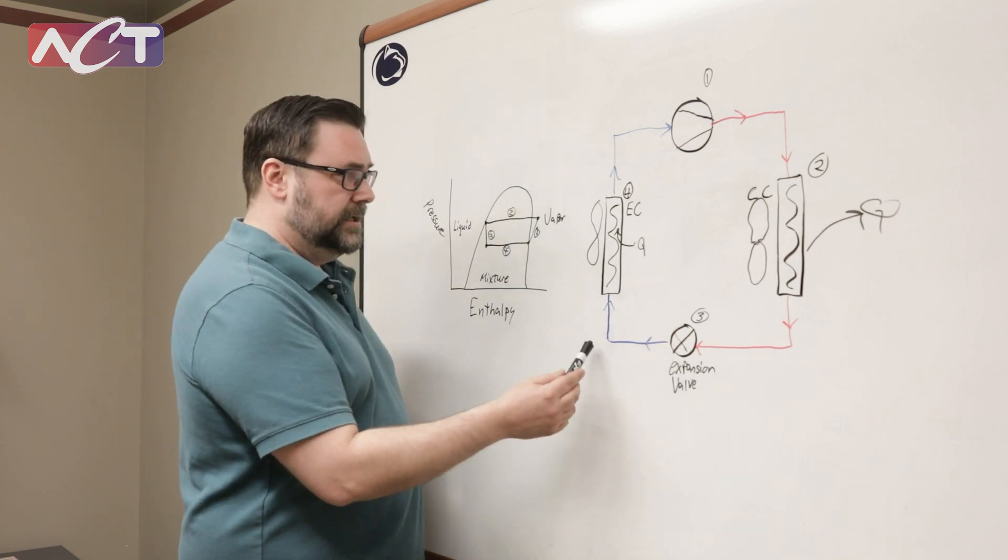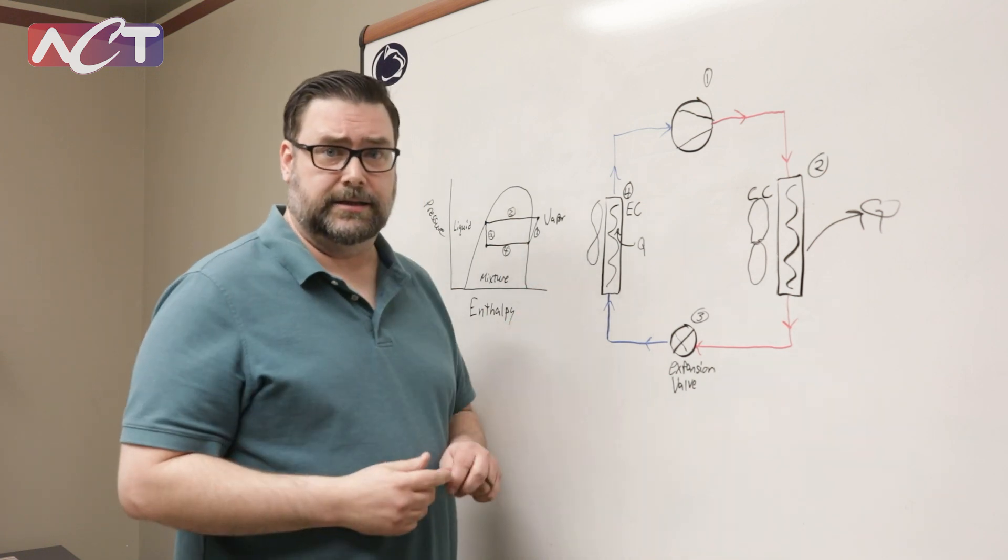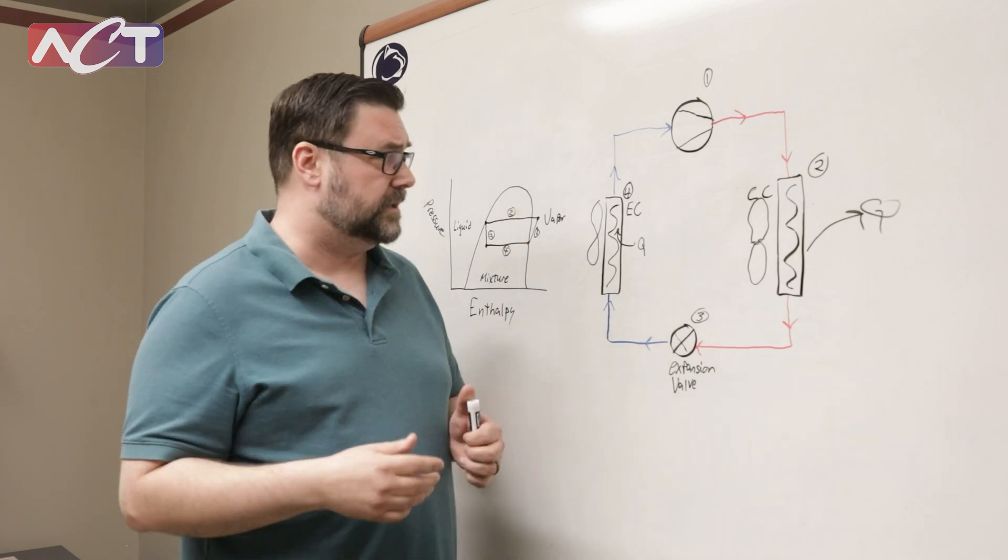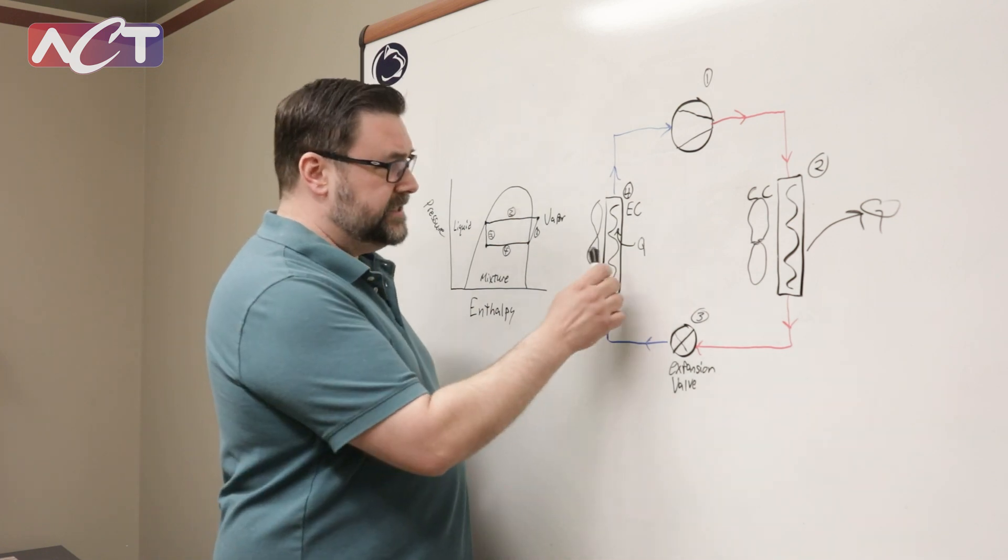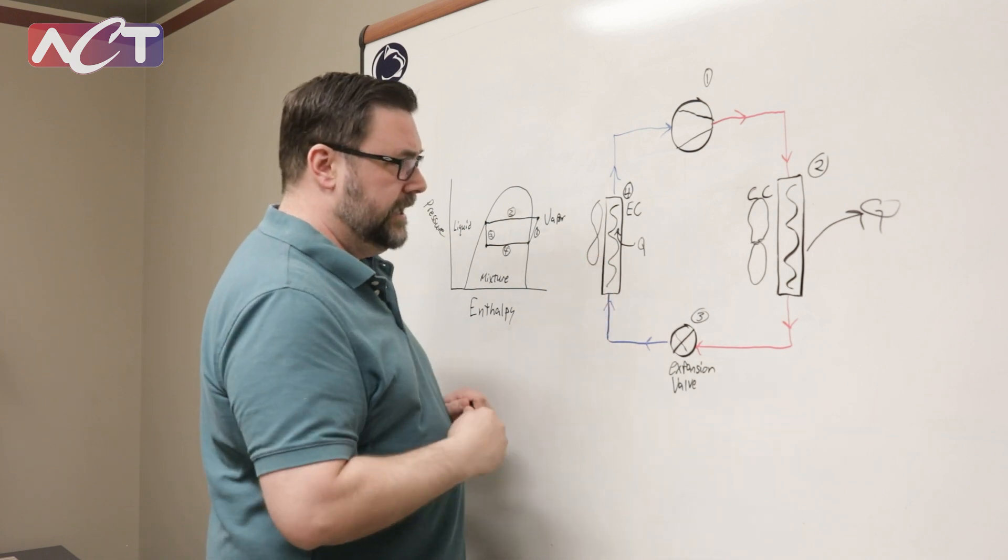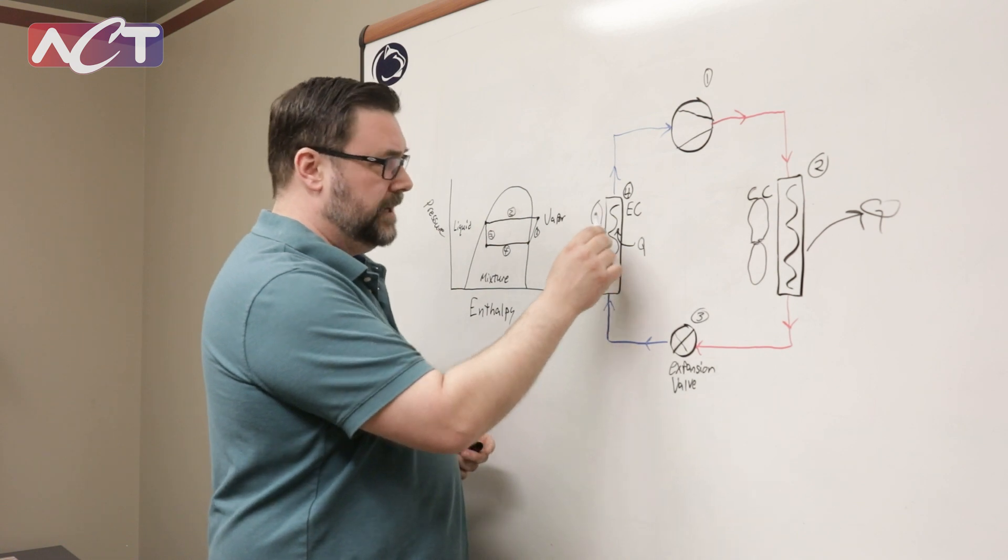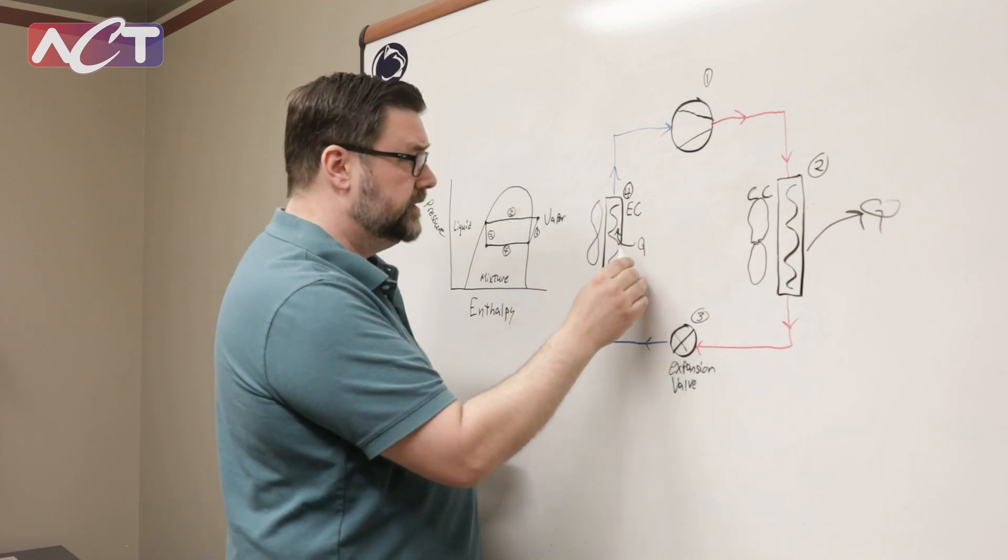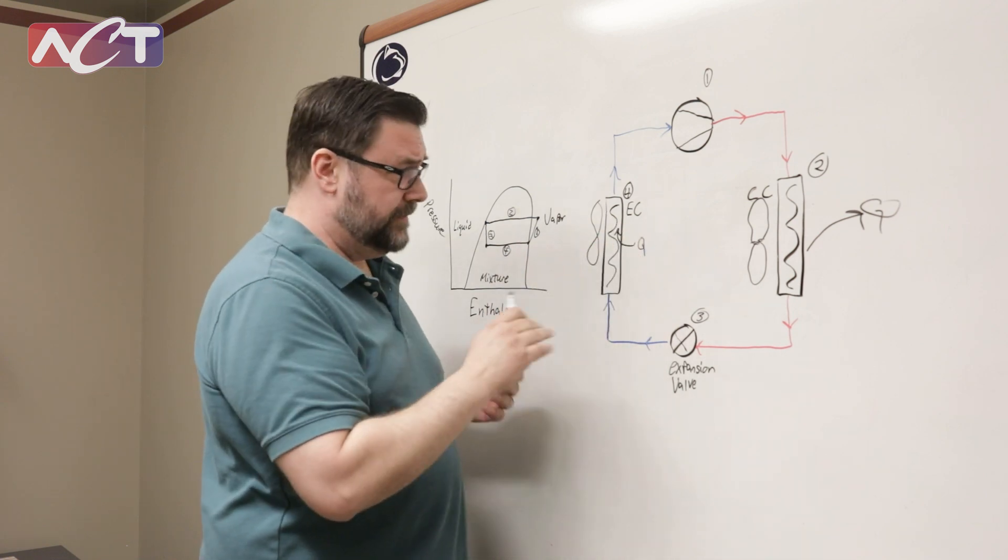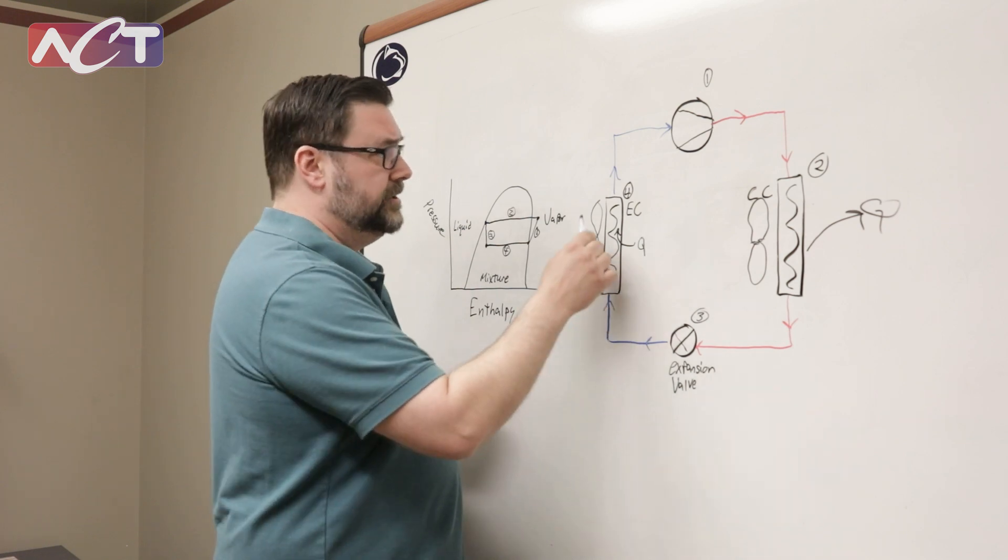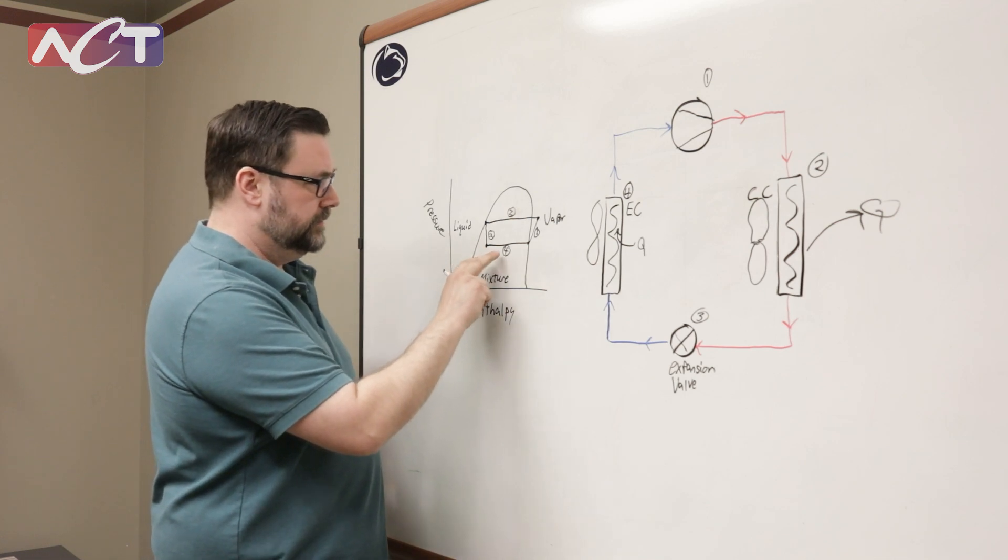So we're going to take that mixture and we're going to take it over to our evaporator coil. Now this is what you would have inside the house where it would be in your basement or wherever it's located, that is a cold coil that the air is blown across. So because it's colder than the environment that it's in, energy is going to flow from the environment into that coil and will get absorbed by the working fluid which is the refrigerant at this point.